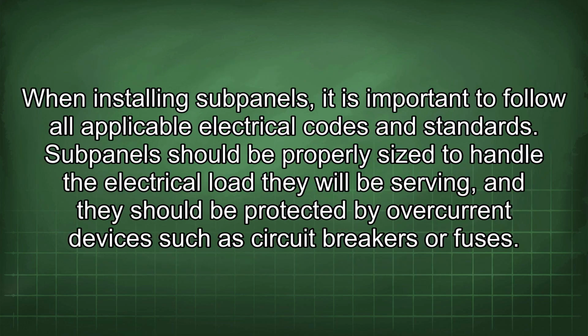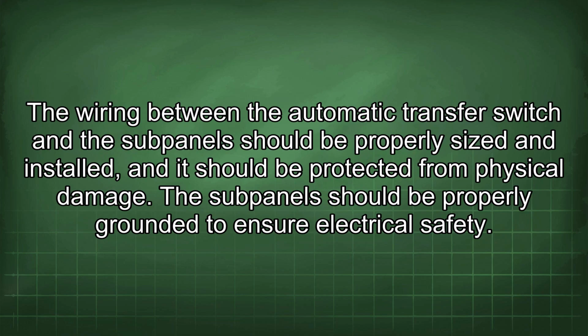When installing subpanels, it is important to follow all applicable electrical codes and standards. Subpanels should be properly sized to handle the electrical load they will be serving, and they should be protected by overcurrent devices such as circuit breakers or fuses. The wiring between the automatic transfer switch and the subpanel should be properly sized and installed, and it should be protected from physical damage. The subpanel should be properly grounded to ensure electrical safety.